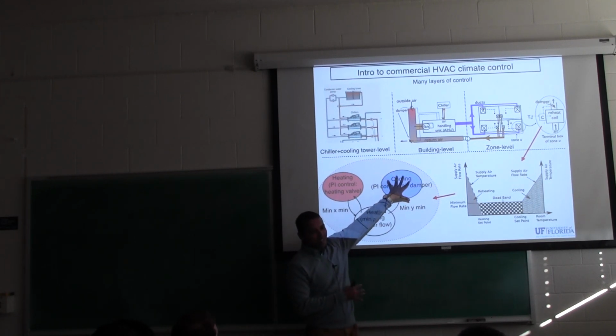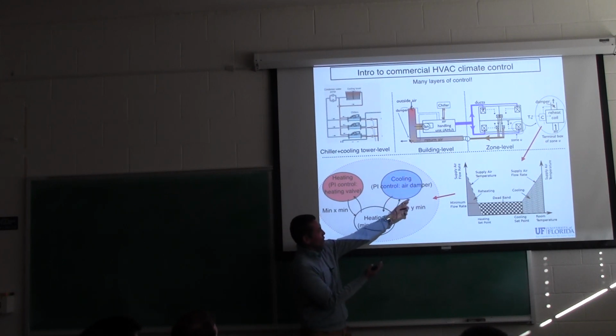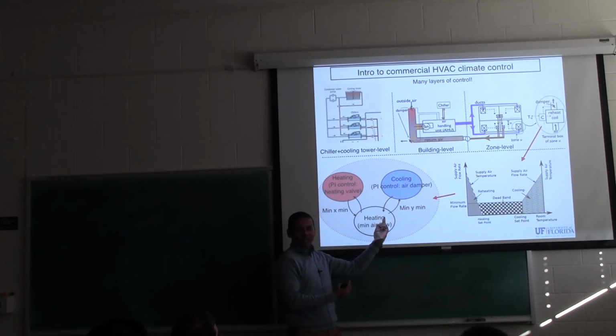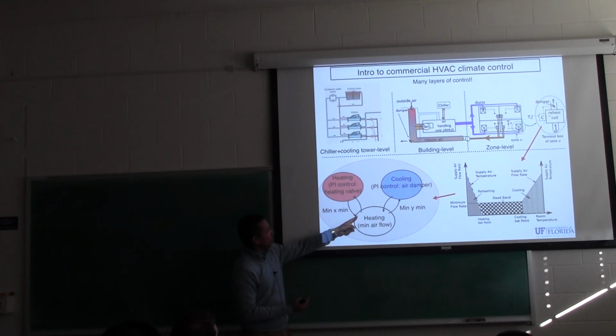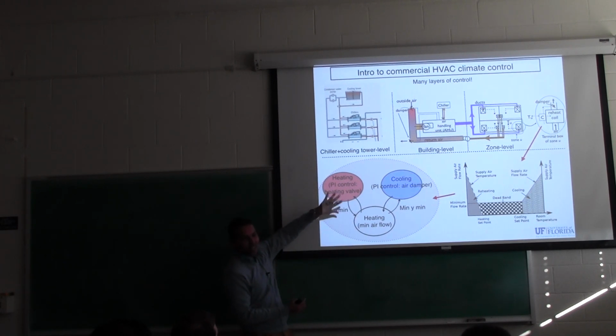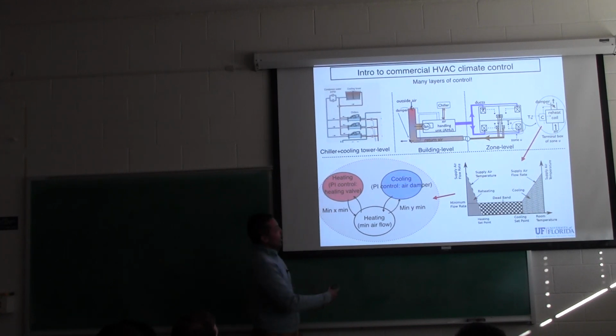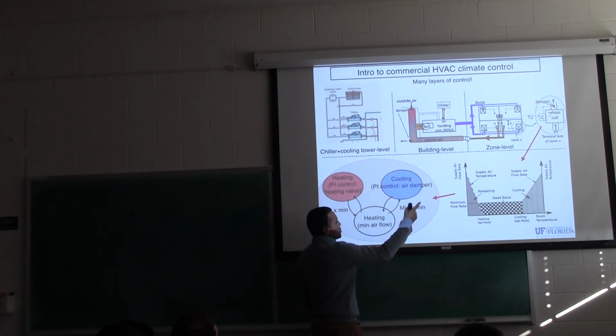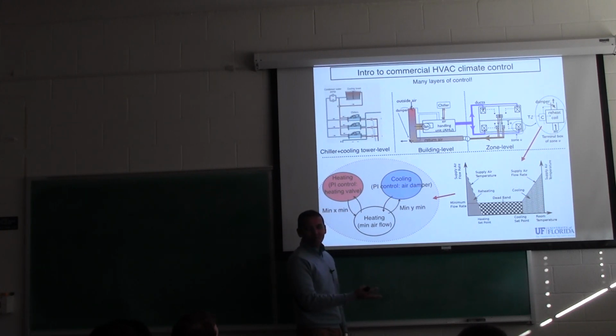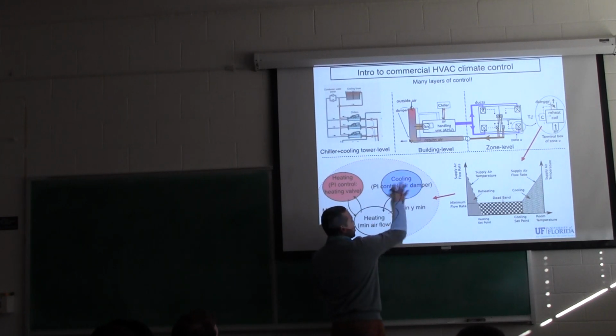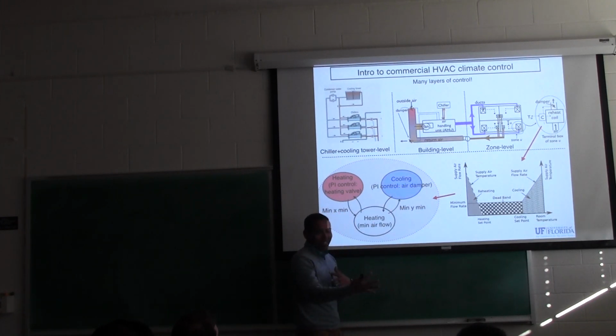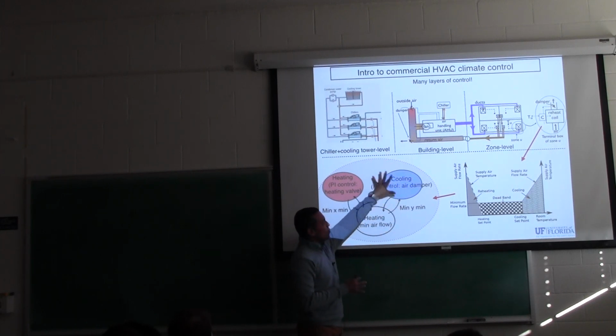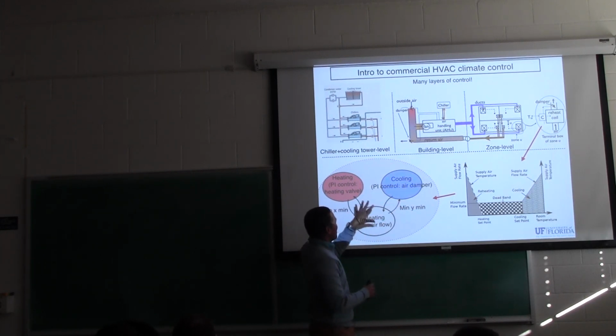This is one dynamic system here. And then if the temperature becomes colder, it transitions back to this mode. If it's too cold, then it transitions to the heating mode. That's another PI controller, with a different set of gains, another dynamic system. And then to avoid this frequent switching back and forth, there are these dwell time conditions. So if it transitions into one mode, it has to spend at least 10 or 15 minutes before it transitions back.